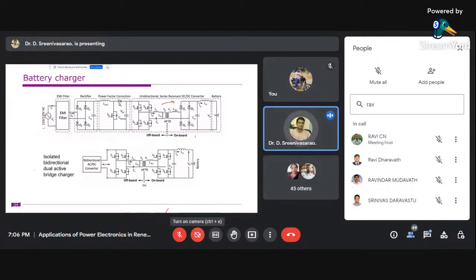And we have another solution, which is for bidirectional power flow. So we have this bidirectional AC-DC converter. That means AC to DC conversion. The DC is available and is converted to high frequency AC, and this high frequency AC is converted back to DC, and it is charging the battery.